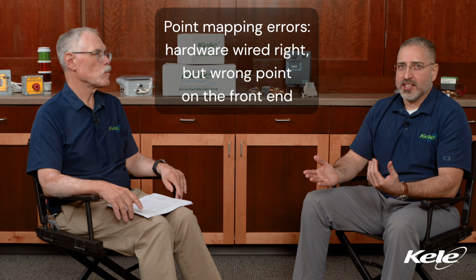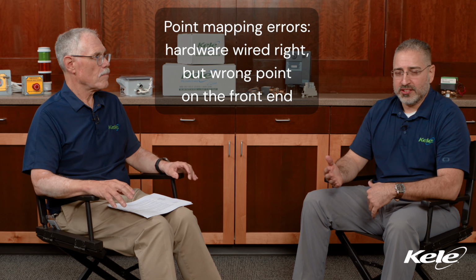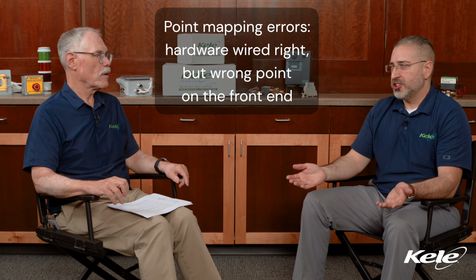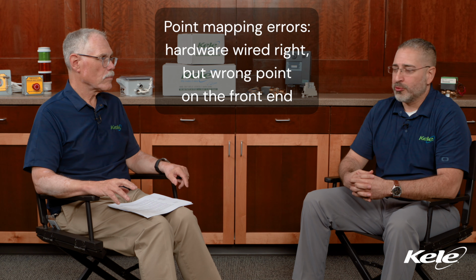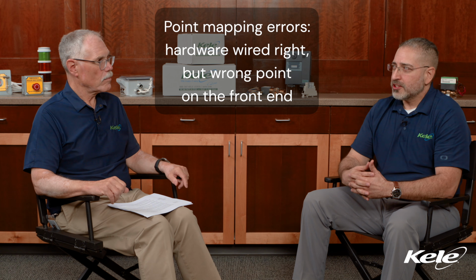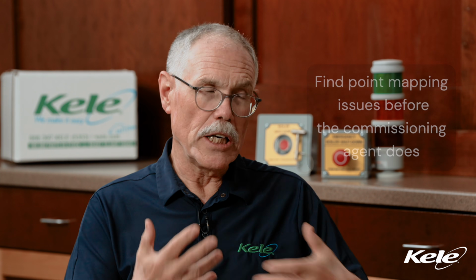Now when all that goes smoothly, the commissioning agent checks and all the actual work, the programming, is in place. But a lot of times the point mapping on the software side is off. So you've got everything wired up right, it functions as needed, but when you look at the front end, particular points look similar in value. Say a temperature, but it's the wrong temperature and in the wrong spot—you might be reading mixed air temperature and your system says it's the discharge air temperature. That's not going to work. You need to make sure those points are mapped correctly, and it's best to find that out before the commissioning agent shows up.